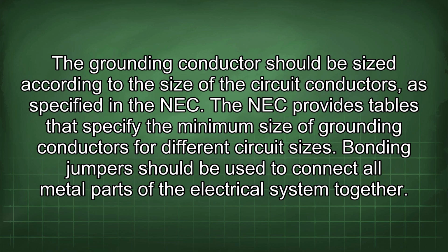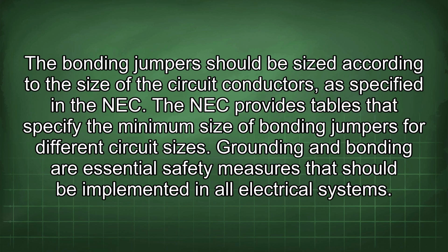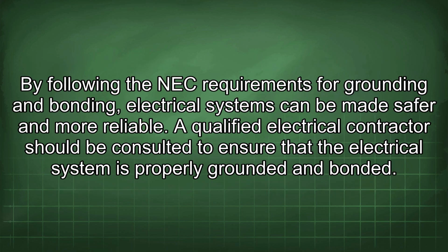Bonding jumpers should be used to connect all metal parts of the electrical system together. The bonding jumpers should be sized according to the size of the circuit conductors, as specified in the NEC. The NEC provides tables that specify the minimum size of bonding jumpers for different circuit sizes. Grounding and bonding are essential safety measures that should be implemented in all electrical systems. By following the NEC requirements for grounding and bonding, electrical systems can be made safer and more reliable. A qualified electrical contractor should be consulted to ensure that the electrical system is properly grounded and bonded.